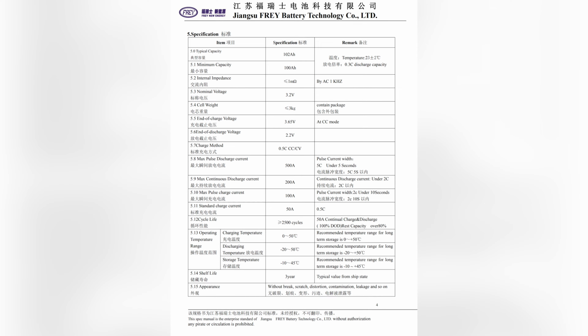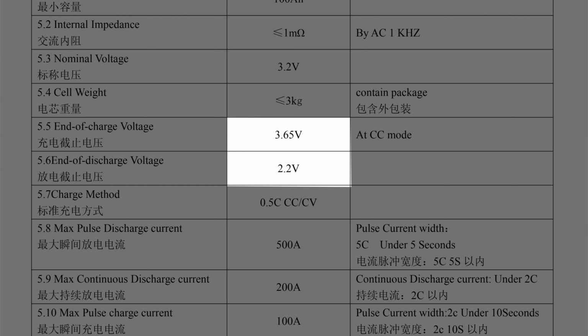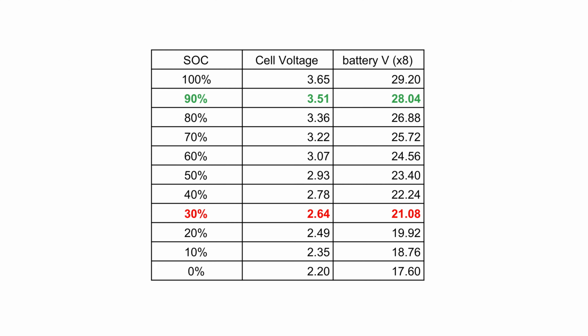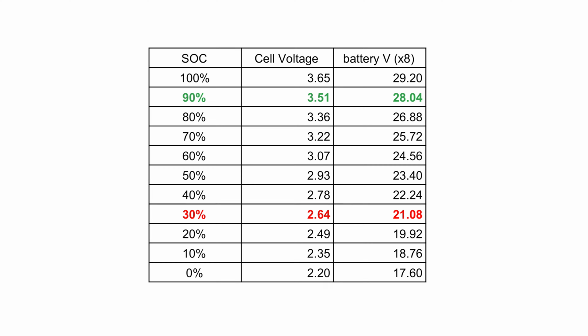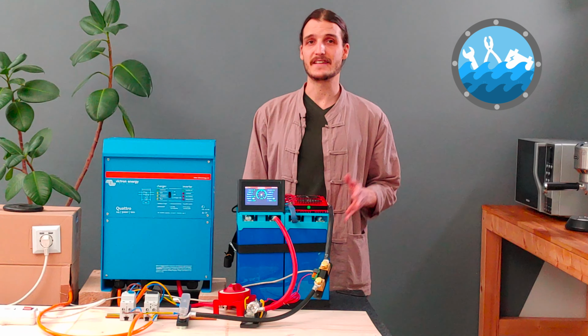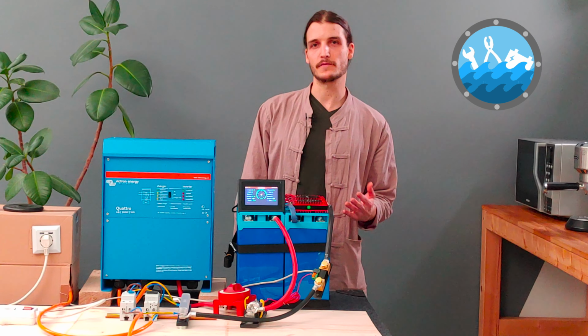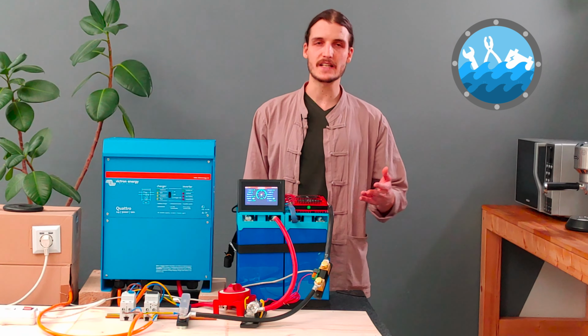For our battery, these values are 3.65 volt at 100% SOC and 2.2 volt at 0% SOC. With this, I was able to draw a simple table which gives me the voltage for a given value of state of charge. I then program these numbers into the BMS of the battery and our Victron inverter charger, so that the battery cannot get charged or discharged beyond those voltage values.